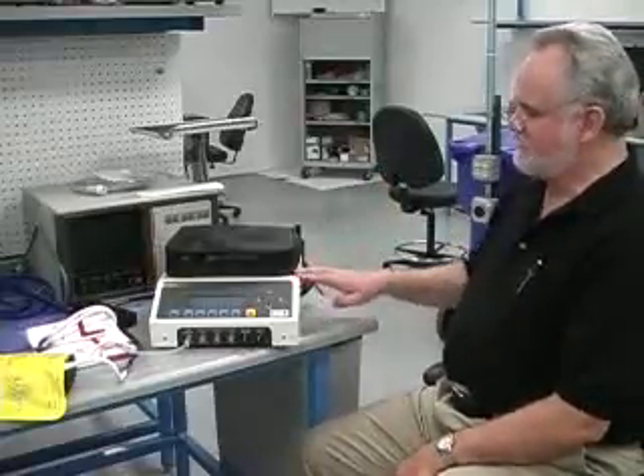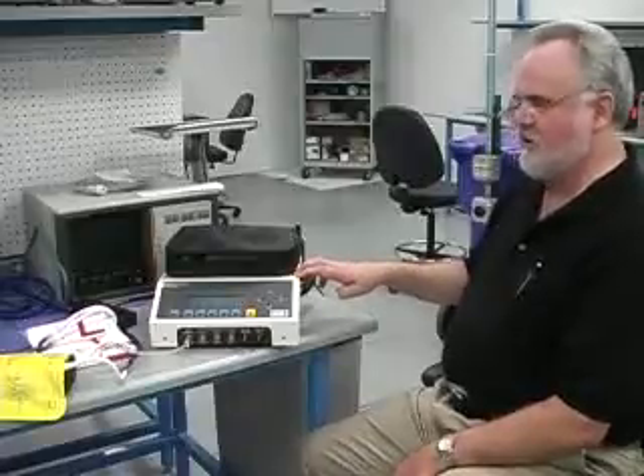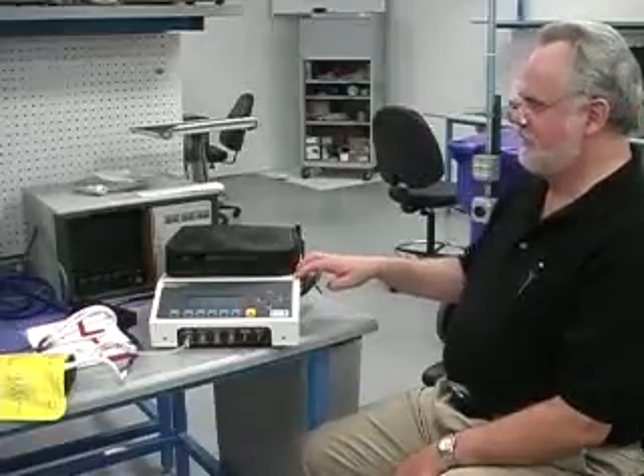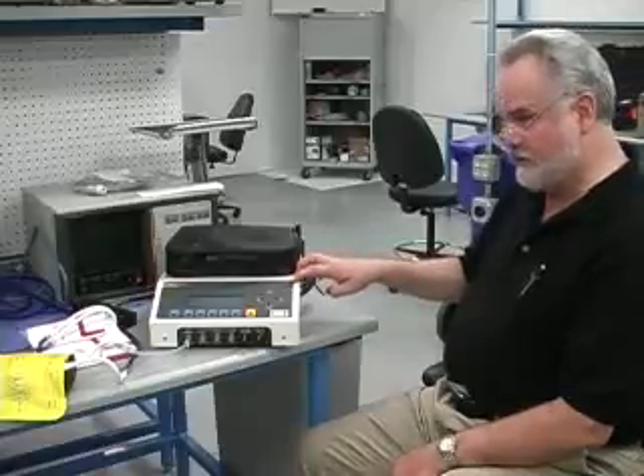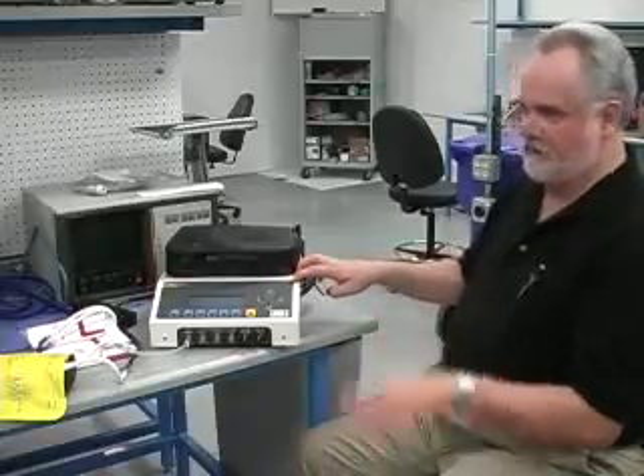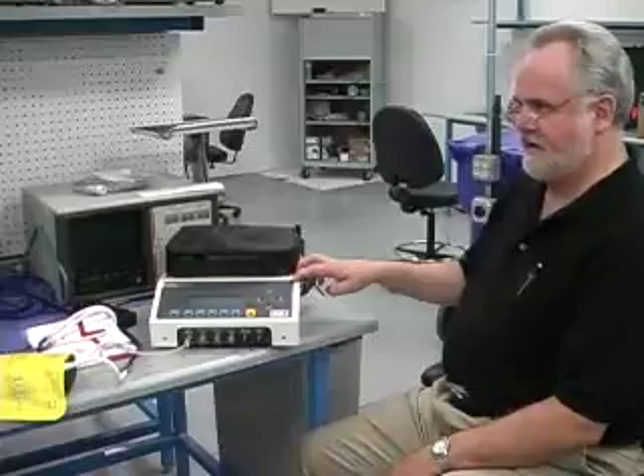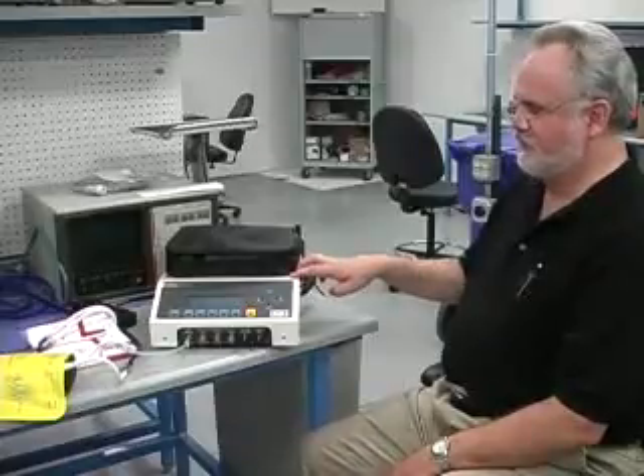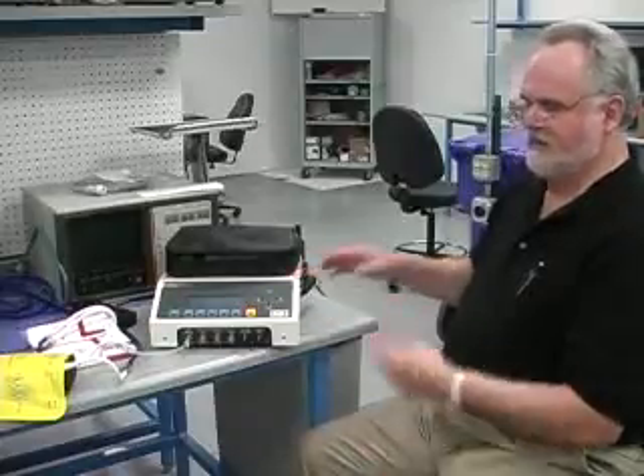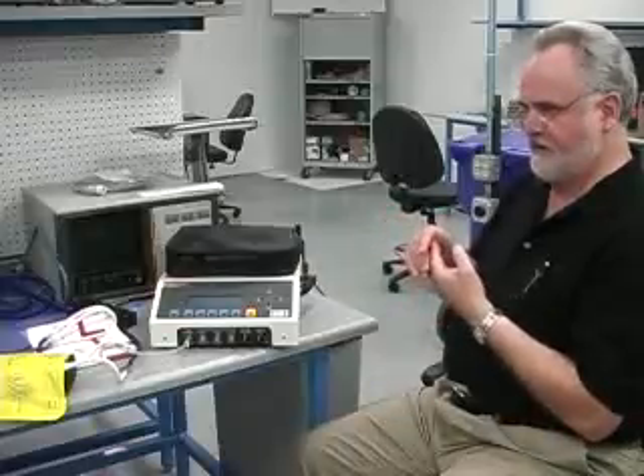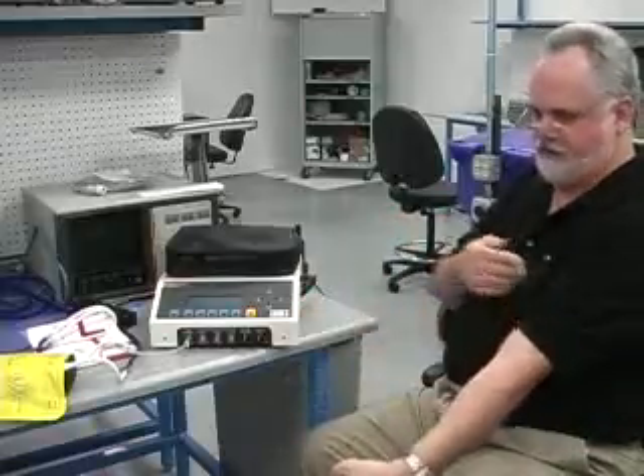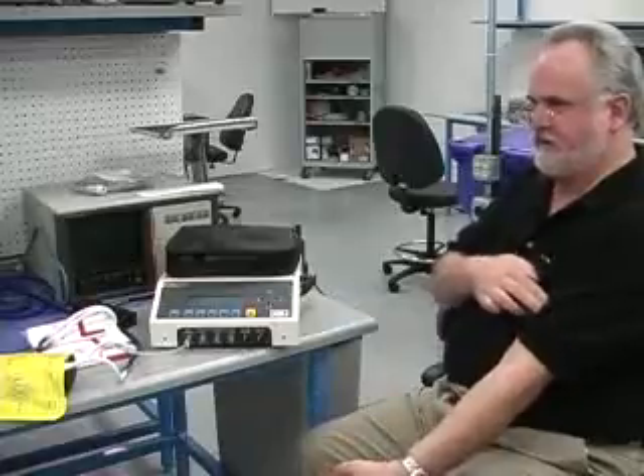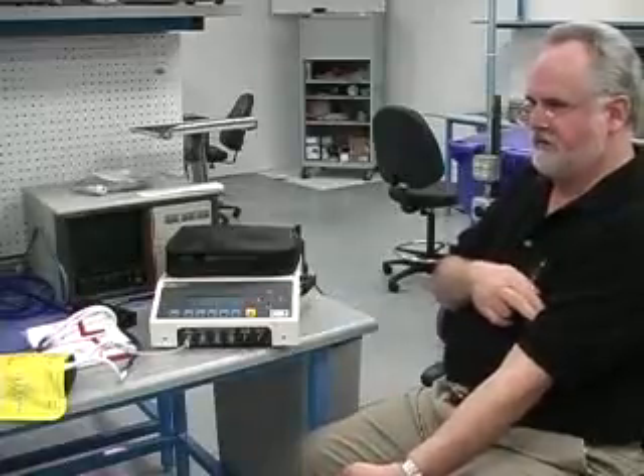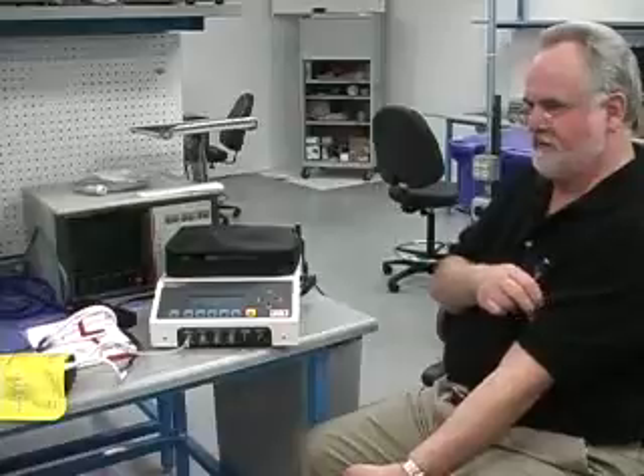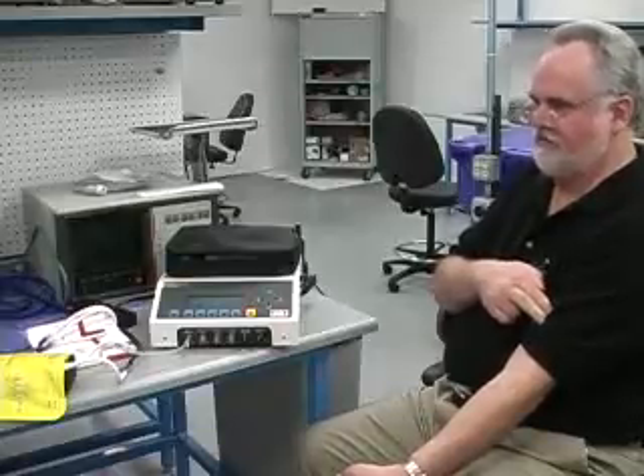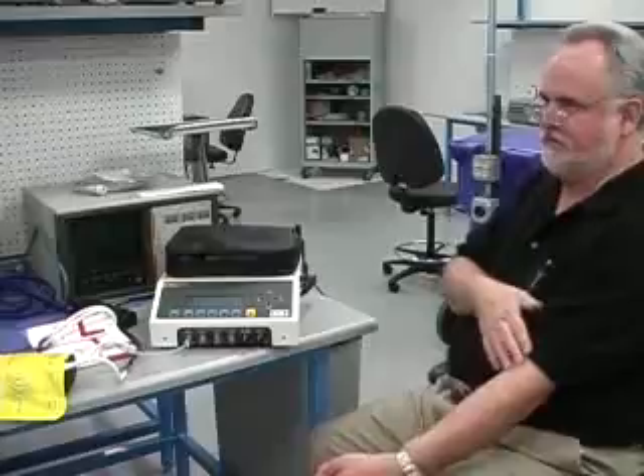We did have an auscultatory option for this a long time ago, but it was for the IVAC model 4200. That was dropped quite a while ago. The IVAC 4200 was designed to work primarily as an auscultatory type, and it actually has a little force transducer in the cuff that looked for the wall movement. But if it didn't get a good signal from the sensor, it would default to an oscillometric method.